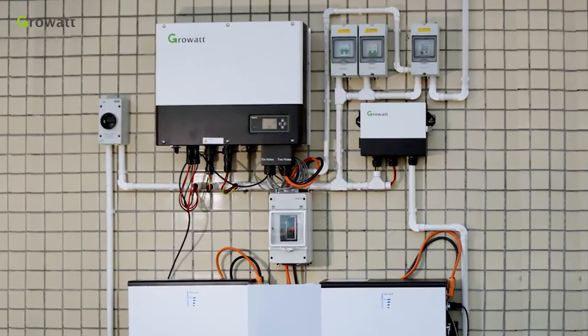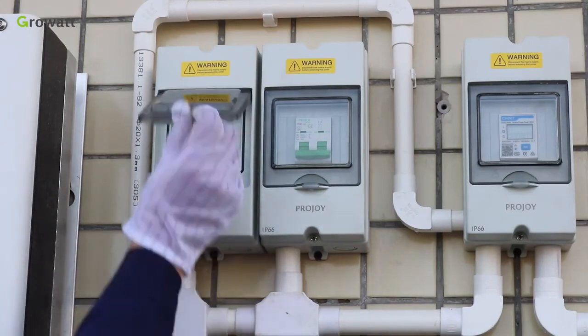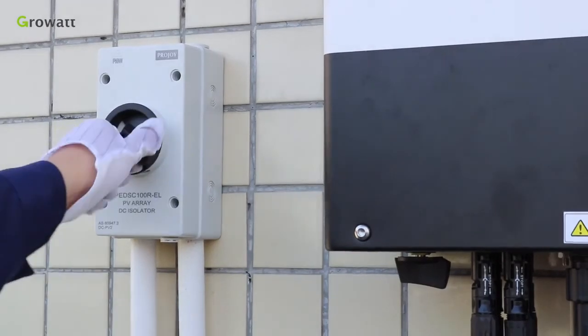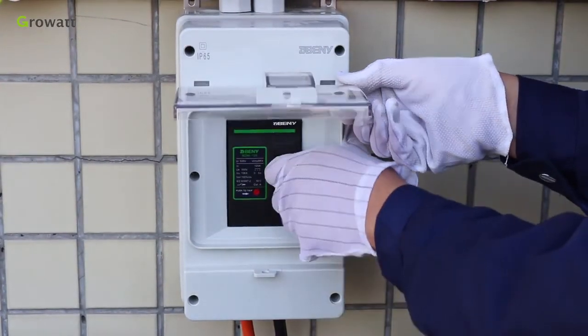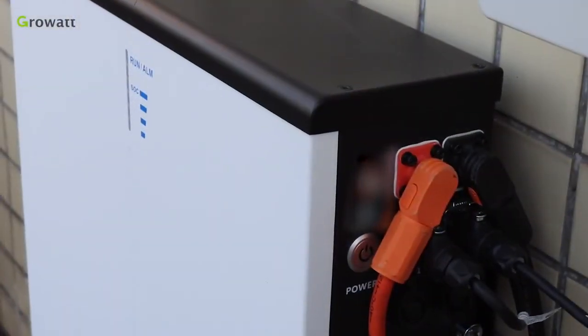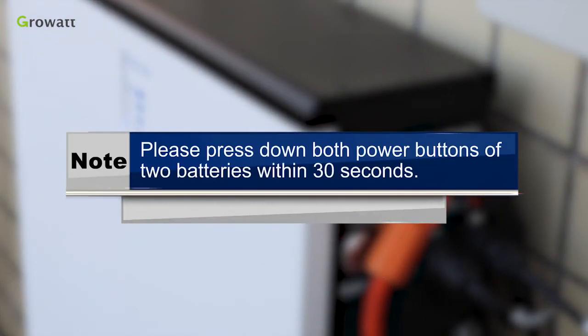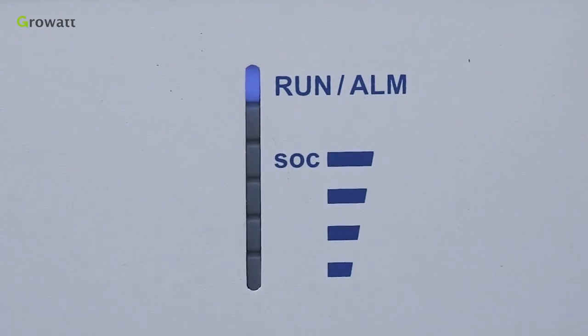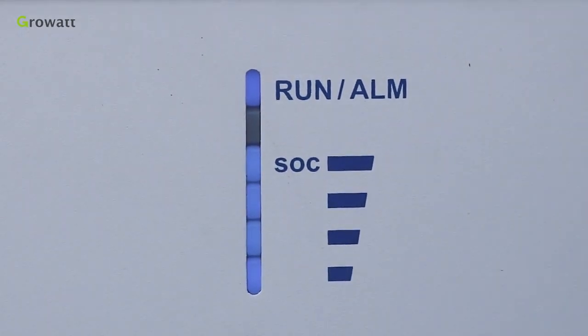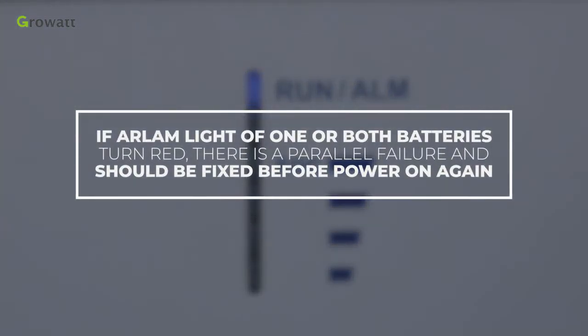After all installations are finished, here are the steps to power on the whole system. Step 1: turn on the AC breaker between the inverter and grid. Step 2: turn on the DC breaker of solar input and the PV switch of the inverter. Step 3: turn on the DC breaker for the battery system. Step 4: press the power button of both batteries within 30 seconds and observe the LED indication. If the RUN light on both batteries flickers five times, both battery systems powered on successfully and communication between the two batteries is established. If the alarm light turns red, there is a parallel failure that must be fixed before powering on again.